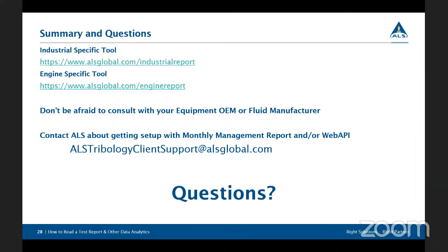We've got a question from Vladimir here. What interval of new oil data for metal contamination and additive parts tells us this data is not normal? So Vladimir, we get that data from two different places. One, we can get it directly from the OEM, the original equipment manufacturer, who will provide it to us. They'll say, here's what we expect to be normal wear rates.